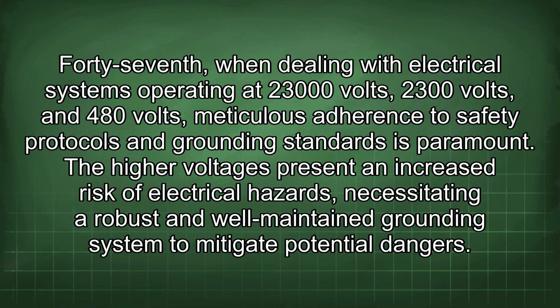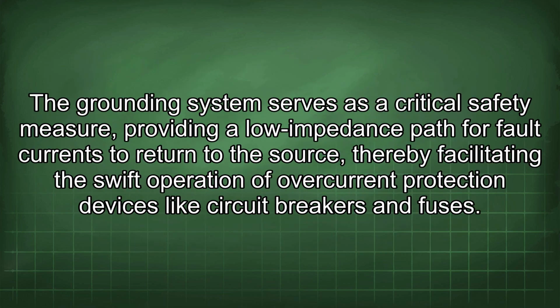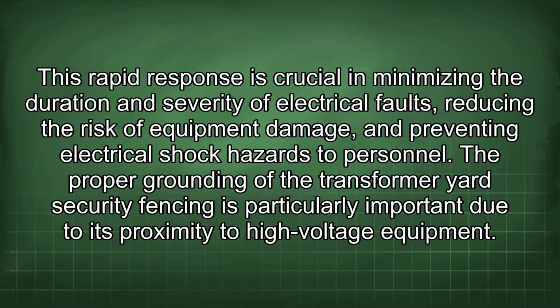47th. When dealing with electrical systems operating at 23,000 volts, 2300 volts, and 480 volts, meticulous adherence to safety protocols and grounding standards is paramount. The higher voltages present an increased risk of electrical hazards, necessitating a robust and well-maintained grounding system to mitigate potential dangers. The grounding system serves as a critical safety measure, providing a low impedance path for fault currents to return to the source, thereby facilitating the swift operation of overcurrent protection devices like circuit breakers and fuses. This rapid response is crucial in minimizing the duration and severity of electrical faults, reducing the risk of equipment damage, and preventing electrical shock hazards to personnel.